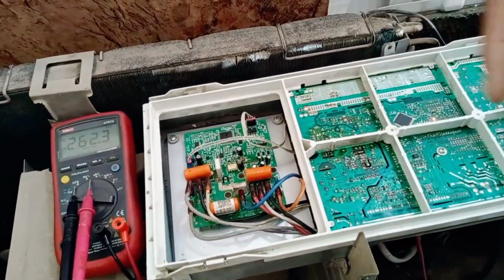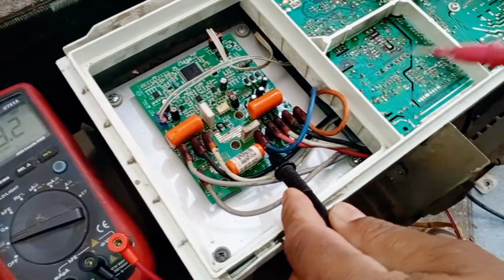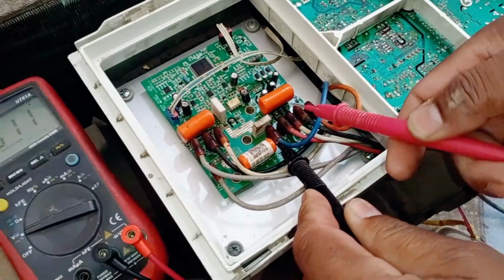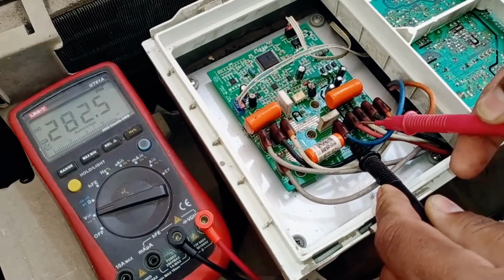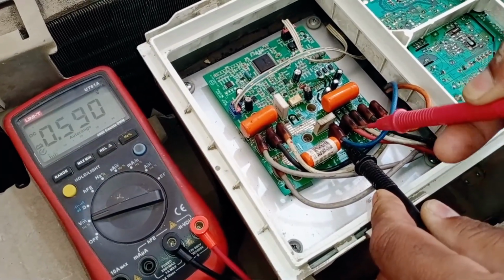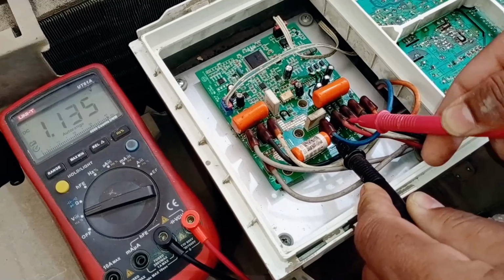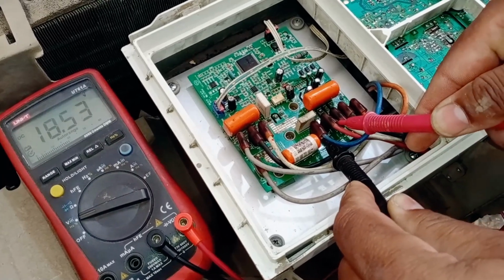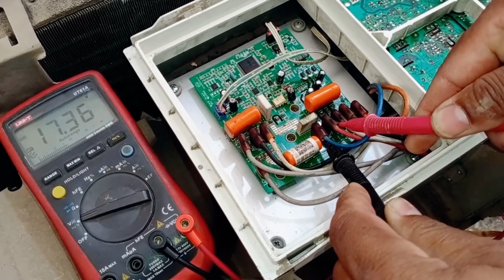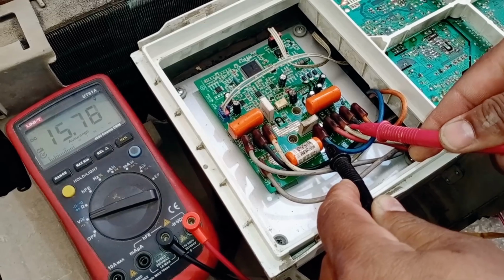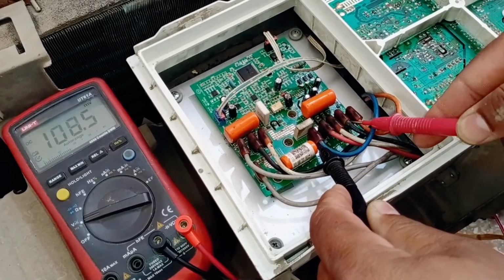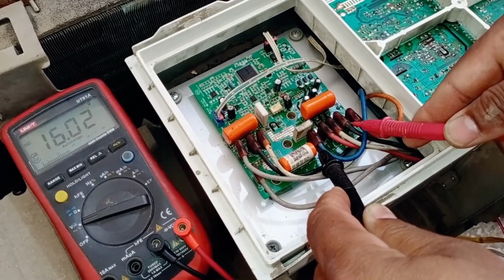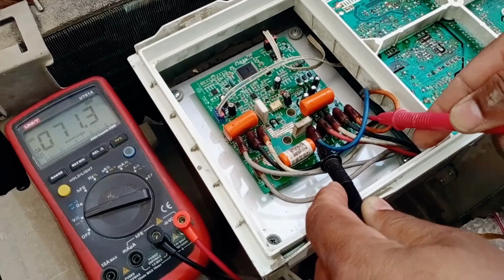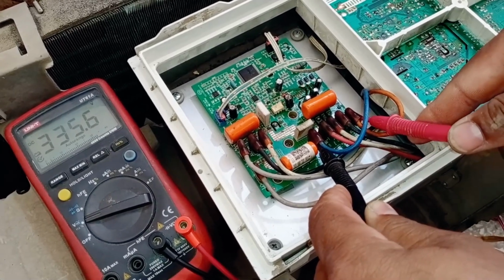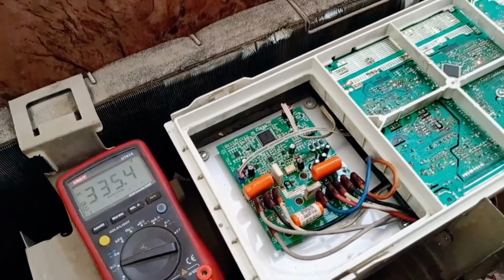Now, let me show you what the issue is. I've reattached the black probe to the neutral, and I'll check the U, V, and W terminals with the red probe. Now, no voltage is shown on this terminal, which means this circuit board has hung, but sometimes the voltage spikes, like right now it's showing 17 volts. The next terminal has 15 volts, and the terminal after that is also showing 15 volts. Now, the last terminal is reading 335 DC volts. Let's wait for a bit and see what happens next.